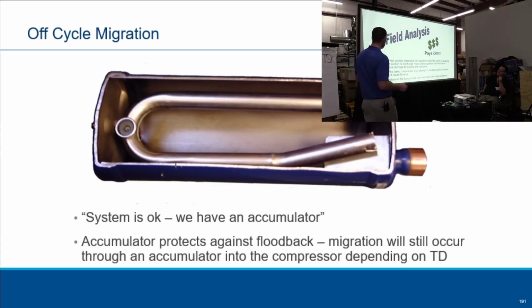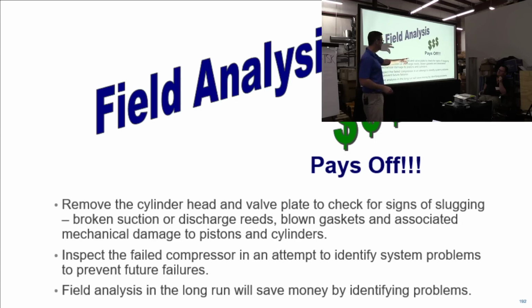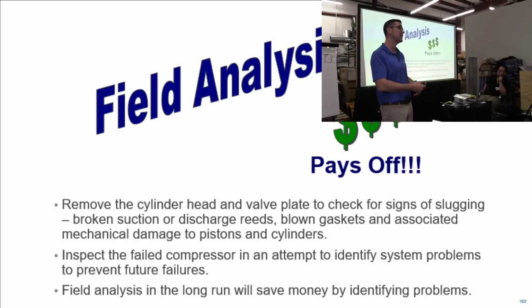Learn from experience. Okay, remove cylinder head. Check for signs of slugging, broken suction, discharge. Field inspect. Big thing is field inspect these compressors, okay? You pull off a head and you see a broken rod, okay, you're going to replace that compressor.